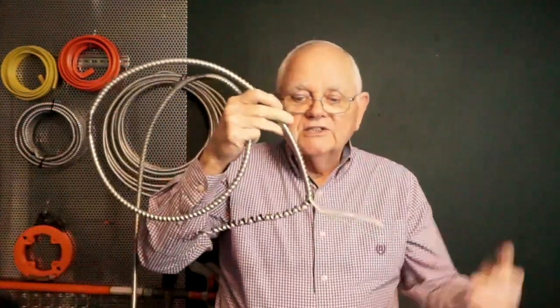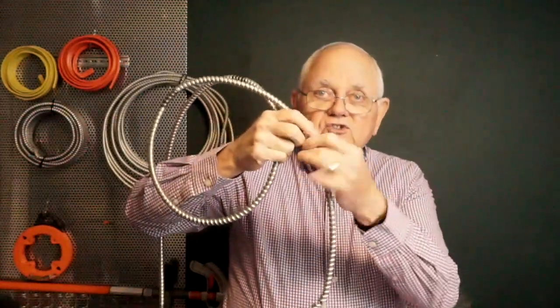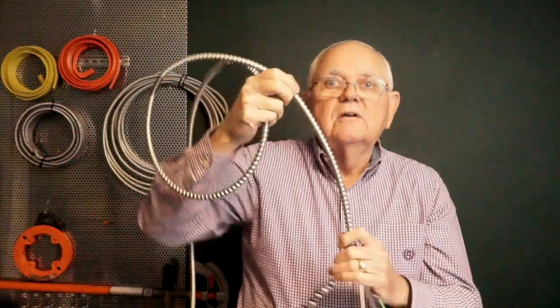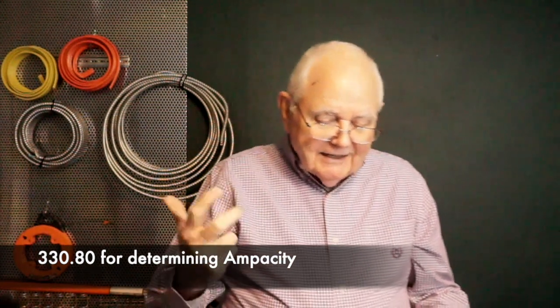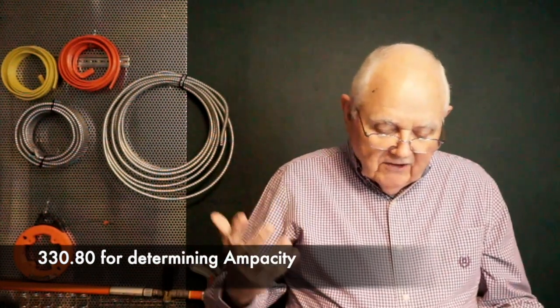Supporting: if I take my MC cable and I run it through some metal framing members that already had the holes in them, and I just lay my cable in those holes, that's support. I haven't secured it to anything. But then when I go into my box, within 12 inches of that box, I'm going to have to get a strap or some other device and secure that cable, probably to that metal framing member or wherever I'm working. So those requirements are covered in 330.30. 330.80 talks about my ampacity requirements, where we've already mentioned some of the particulars of that. And then that takes us into Part 3, which we've already talked about, which is our construction specification requirements.